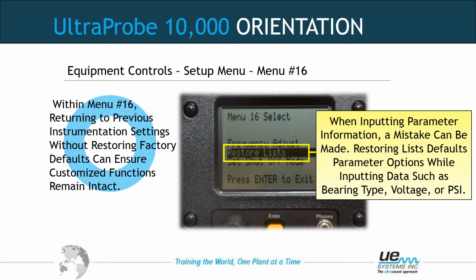If bearing type, you can put what type of bearings: needle, split, spherical, ball, roller, whatever type of bearing you have could be in a drop down, and you actually enter that through the DMS software and load it with the route, and it'll show up in here. Say once you got out there and you really don't like these input list items, you could restore it to the default of NE, not entered. So you'll see NE a lot. That means not entered in this area. Not a lot of people use this.